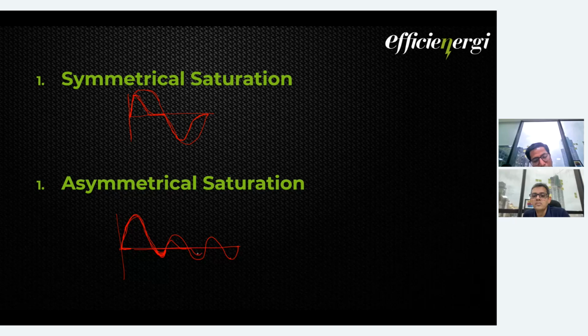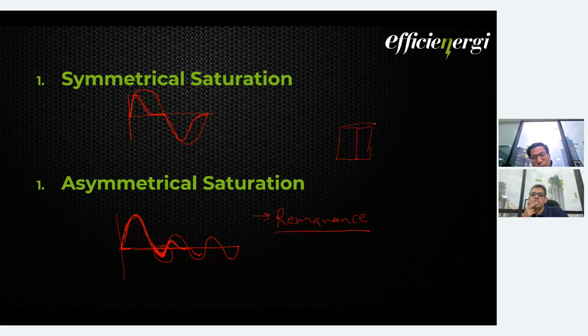In an asymmetrical fault, in the initial cycles you may see the relay showing the correct replica of the primary, but after a few cycles it vanishes and it gets saturated, because there are no dipoles left for the reverse. This also brings us to another topic, that is remanence. If there is remanence inside the core, then again it is as good as this: the dipoles are already aligned and you have very few dipoles left to align. So if there is remanence, it will act as a saturation. On the mitigation part, I will talk about remanence in more detail, but we'll see what remanence means.